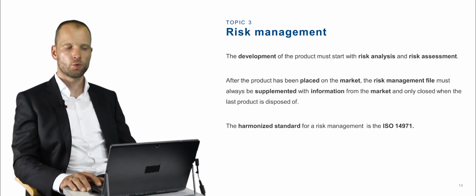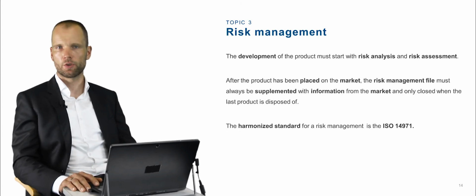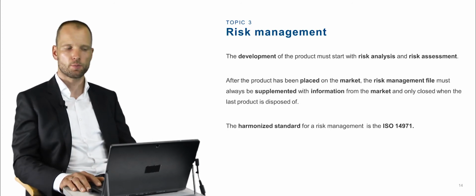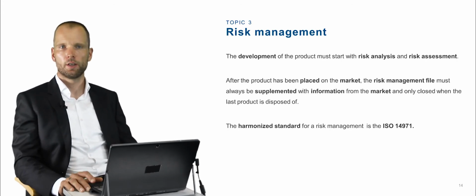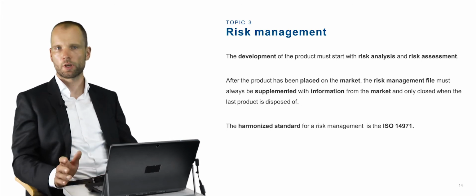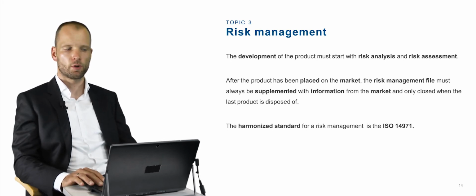Risk management. The development of a product must start with the risk analysis and the risk assessment. After the product has been placed on the market, the risk management file must always be supplemented with information from the market and only closed when the last product is disposed of. The harmonized standard for risk management is the ISO 14971.